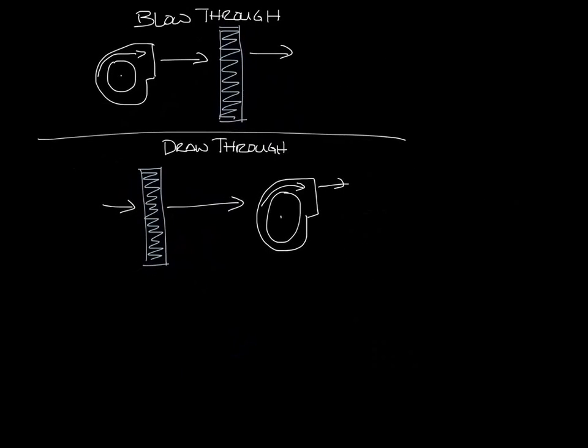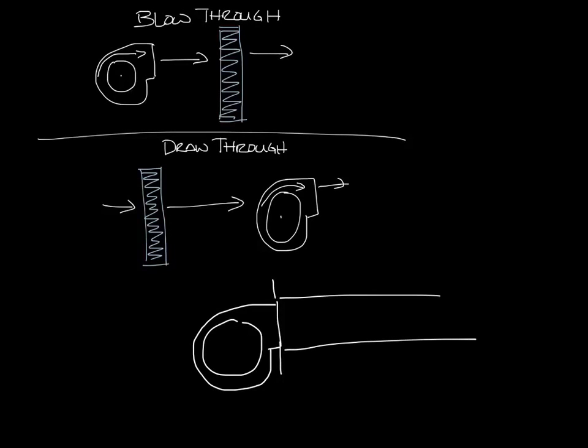Okay, so let me make a little bit of room, and let's just look at a fan. Maybe it's mounted to a discharge panel and connected to some ductwork. So the velocity profile coming out of the blower is going to kind of look like this, where at the top of the blower where the air is coming out has got a higher velocity, and as it moves down the ductwork, it eventually evens out into a more uniform flow. On the inlet side of the fan, the flow is coming in pretty uniform from all sides, so at any point in, say, ductwork over here, it would be about the same velocity.